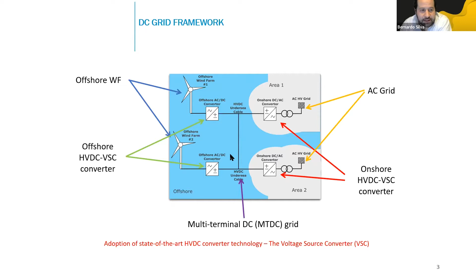If we attain a big deployment of these DC grids and a lot of offshore power coming from these DC grids, we also need to maintain the controllability of the mainland power systems. What is happening onshore, and has been for quite some time, is that onshore wind energy converters are able to provide what is called primary frequency control, now frequency containment reserve, because they sense the frequency at their terminals and can change the pitch angle of the wind turbine blades. If they are operating below the maximum capability curve, they can even provide upwards power control. So when we have an under frequency, we can inject active power by increasing the amount of energy that we are collecting from the wind.